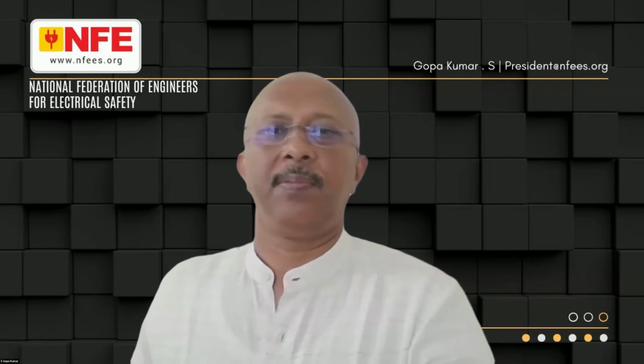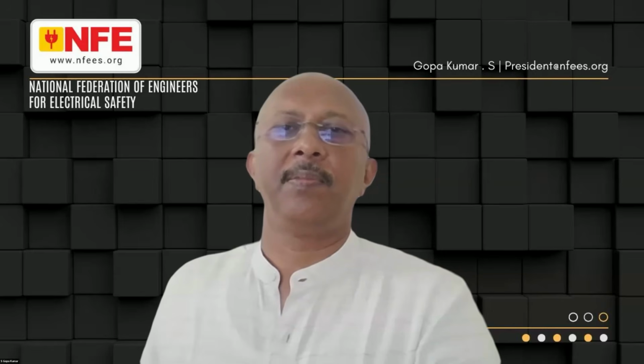Why I am saying the dedicated earth electrode is a misconception: because there are issues like conducted emissions, and electromagnetic and electrostatic coupling. There is a potential existing between voltage source and earth. So this affects the referencing of sensitive electronic devices. Medical diagnostic devices can malfunction because of separate dedicated electrodes. Without addressing the root cause of conducted emissions, electrostatic coupling, and the potential existing between the different earth electrodes, mutual coupling, we can't avoid neutral to earth voltage. Neutral to earth voltage can't be there once you follow the standard practices.